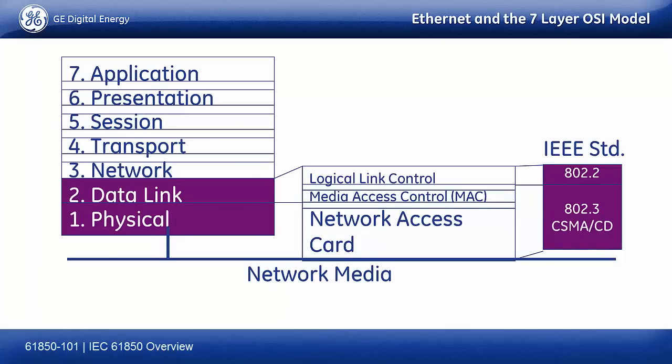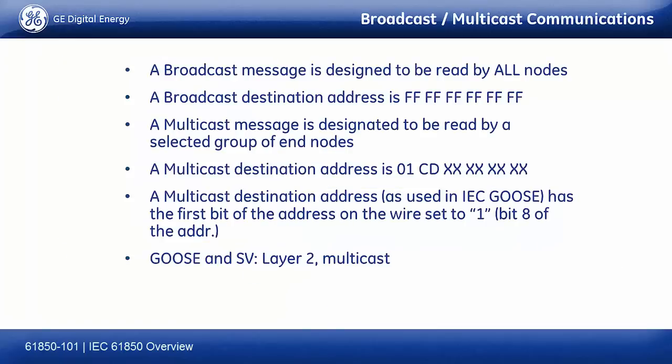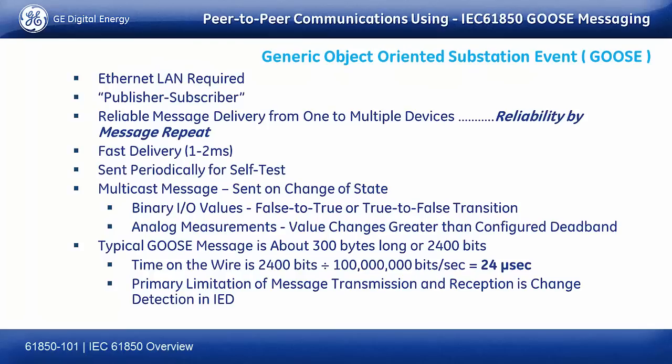We don't have to use IP addressing. And this is where GOOSE resides. I'm at Ethernet, I'm at layer 2, raw Ethernet stuff. What I'm doing with GOOSE, and raw Ethernet means, of course, it can only be switched, it cannot be routed, so it stays inside the substation. Routers don't know what to do with layer 2 only stuff. There's no IP address. So a router gets it, it throws the message into the bit bucket, which is basically the garbage can, so you can only use this, right?